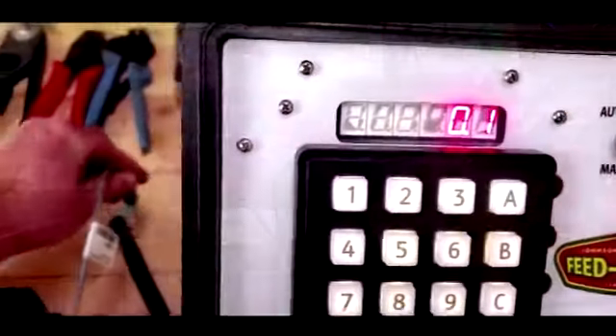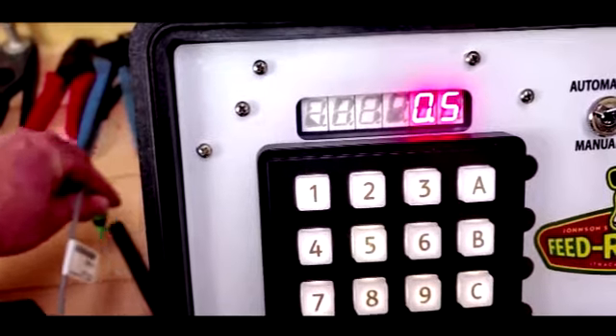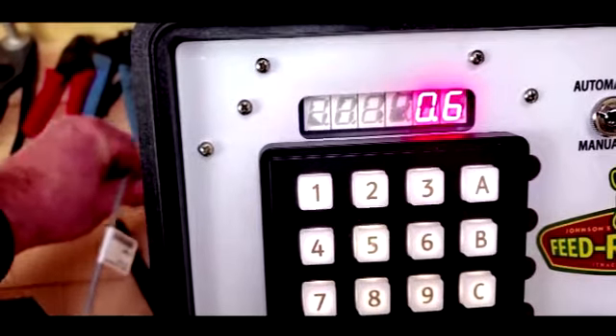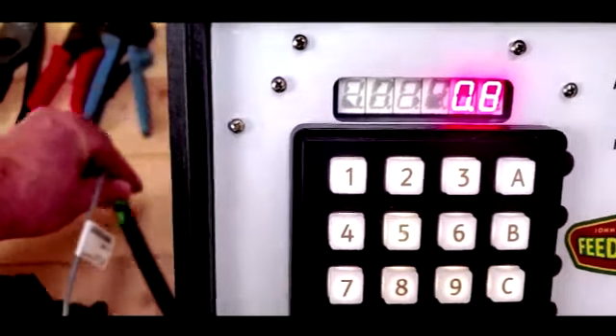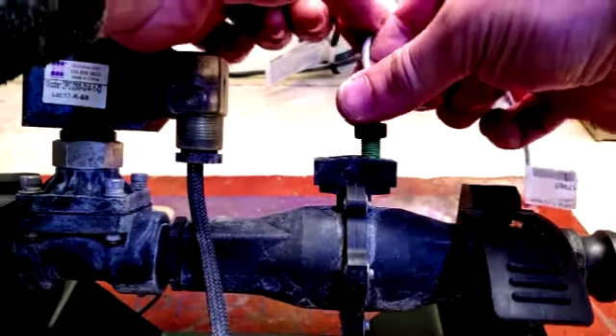Now you see I've got a magnetic clip on the end of my flashlight, and I'm just going to wave that back and forth in front of the end of the sensor. You can see that creates count on the flow, and this is how the flow meter works. So if this is happening, your wiring and your sensor are good.